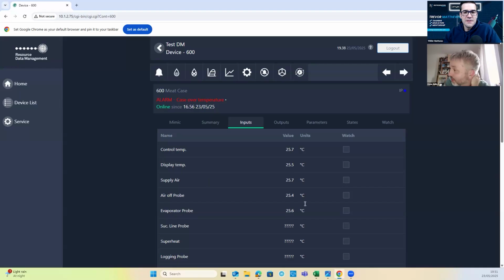What I'm going to do is let the case get cold enough that it's then going to do a defrost. And I'm going to initiate a defrost and check my heaters. If I've got heaters, you can do it with the bottom left button on the controller. Hold it down and it will go into defrost. This one won't because it's too warm, but you can do it on a live one.